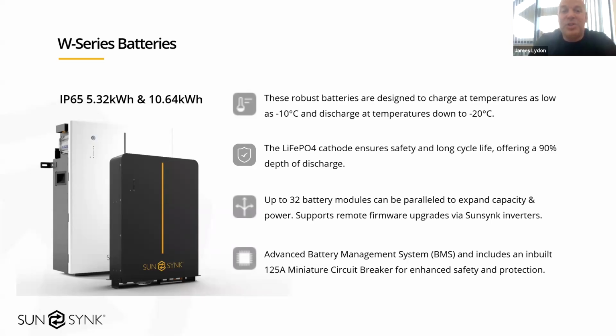You can connect up to 32 of the W series batteries together. So, you can have 32 W10s connected together, giving you way over 320 kilowatt hours of storage. So that is going to be a big system. There's going to be multiple inverters in parallel. You've got all your batteries, but it is possible. And then built into the battery as standard, you've got the advanced BMS. That BMS, the battery management system, is continually monitoring all the individual cell temperatures and the voltages, and if it does see anything out of the ordinary, it will completely shut that battery down. So it's really safe.